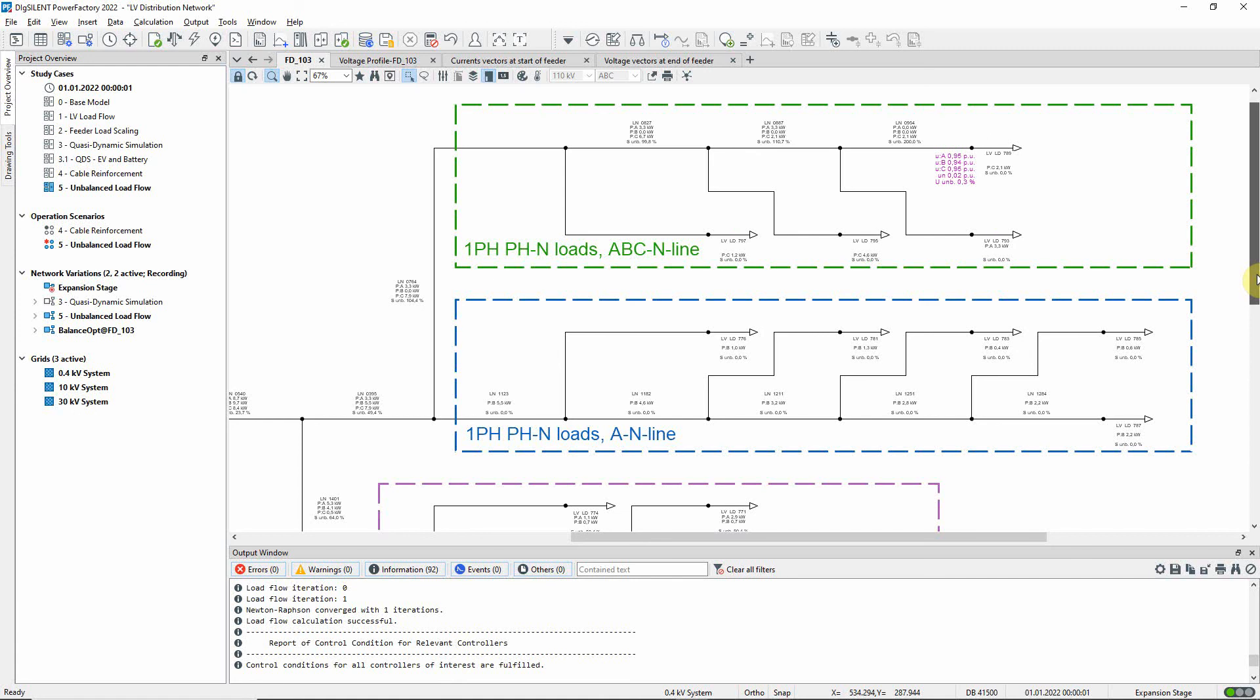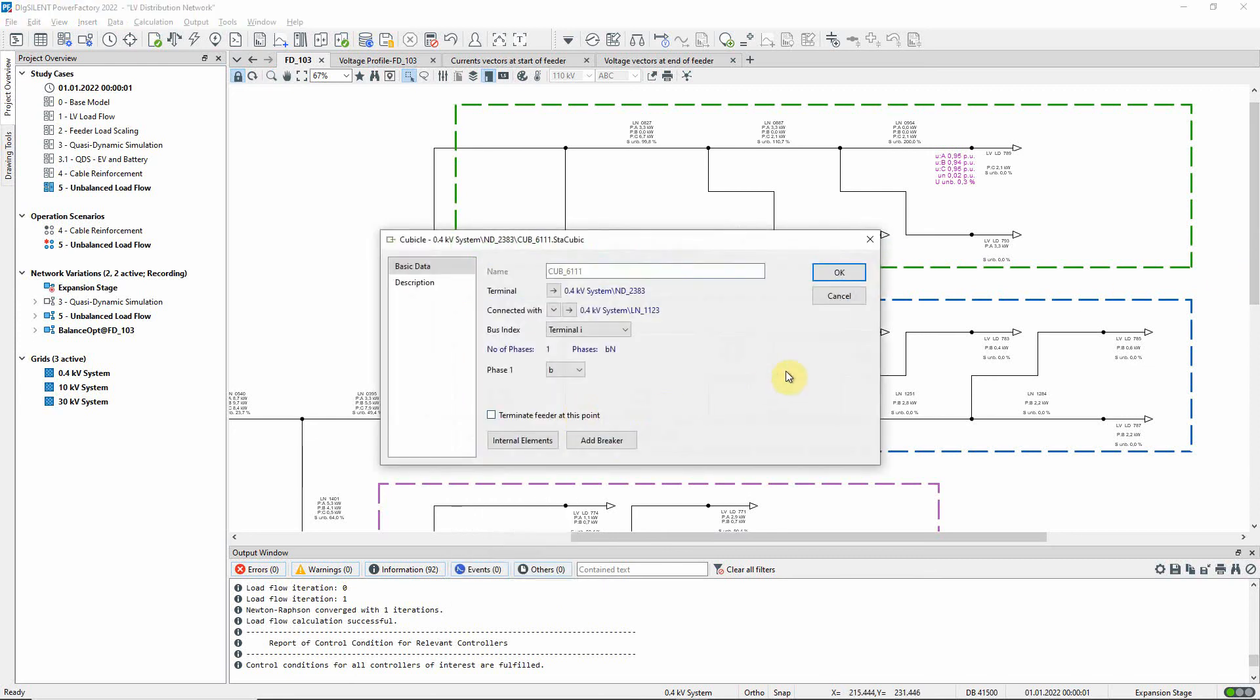In the second branch, all the single phase loads are connected to a single phase line so they couldn't be redistributed. However, the single phase line has been reconnected from phase A to phase B.